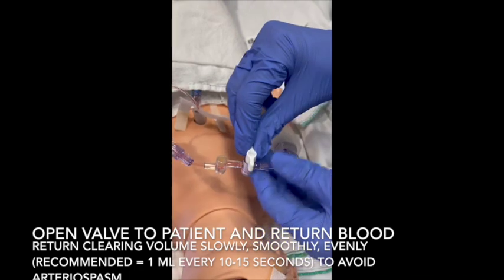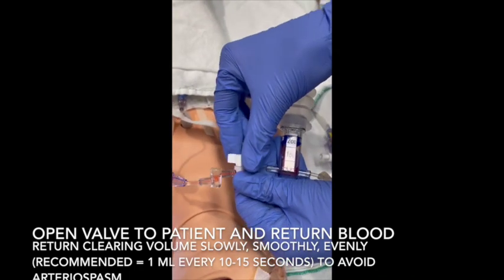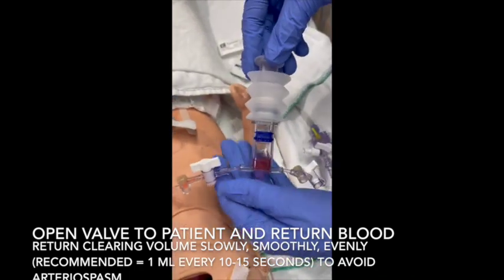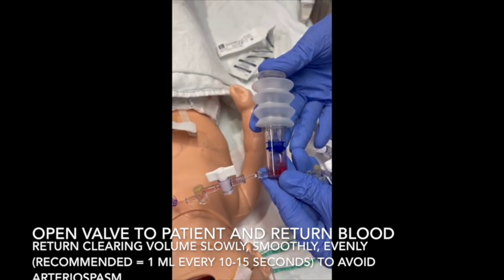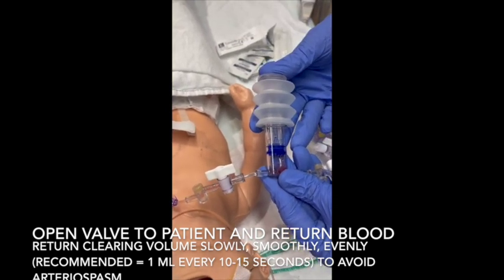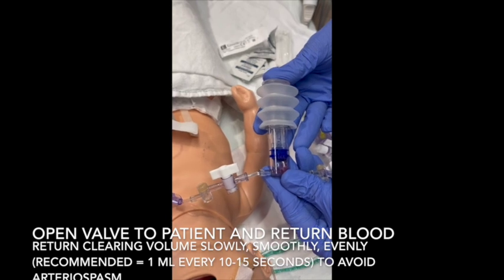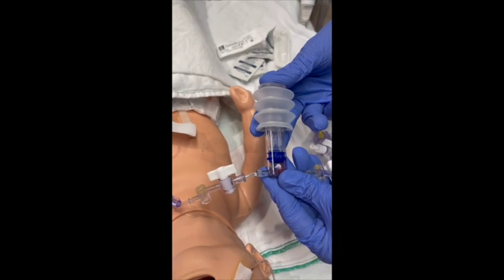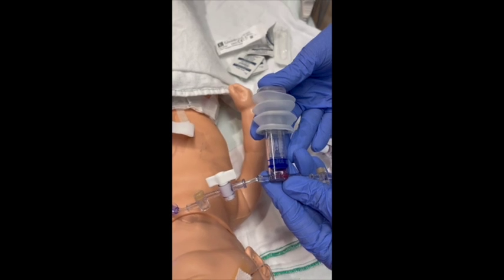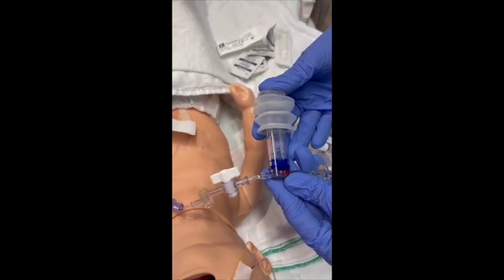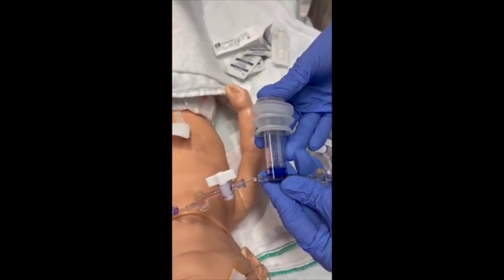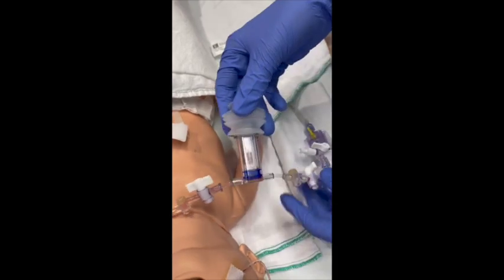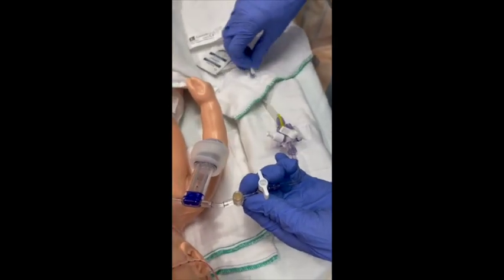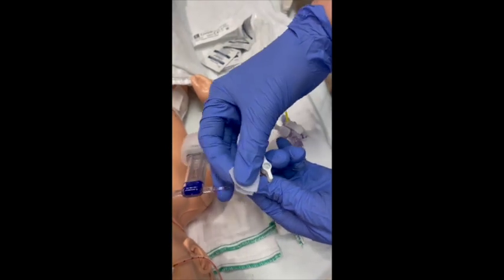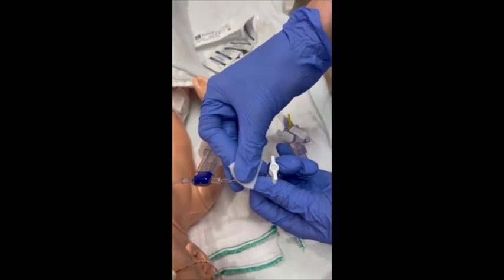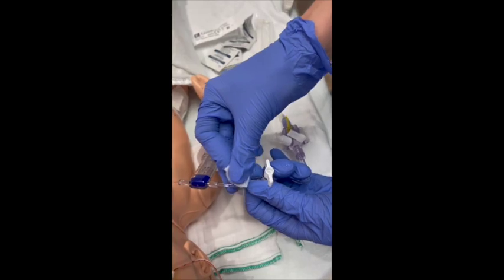Clear the infusion line immediately because stationary blood may result in clot formation. Open the proximal valve by turning handle parallel to the tubing. Return the clearing volume by slowly, smoothly, and evenly pushing down on the plunger of the VAMP Junior until it is fully closed. Recommended return rate is 1 mL every 10 to 15 seconds. Infusing too rapidly or using excessive volumes can cause arteriospasm and subsequent complications.